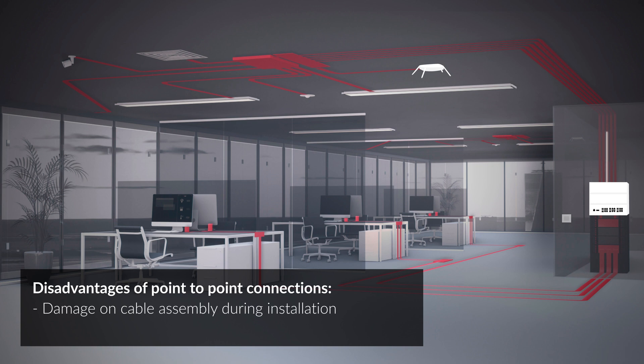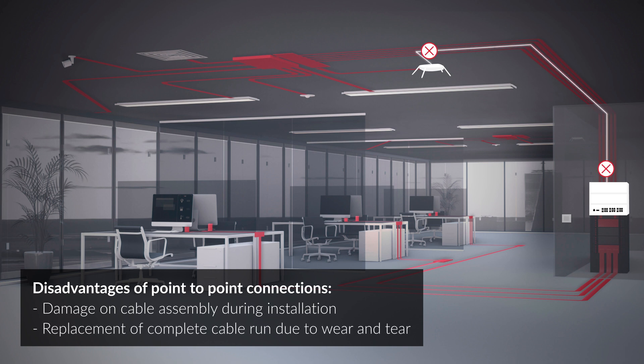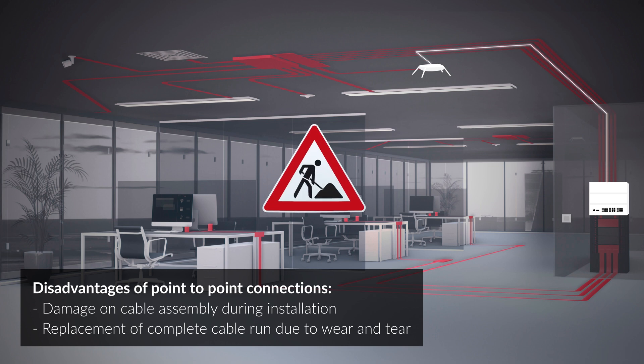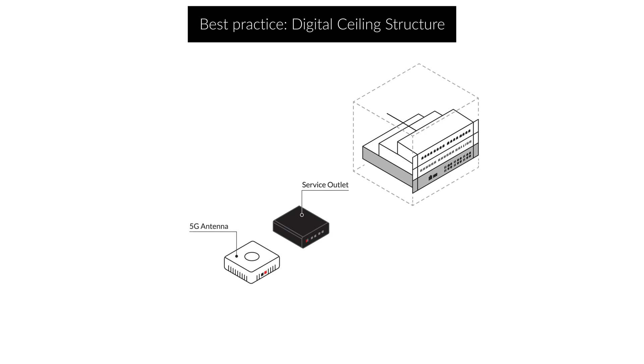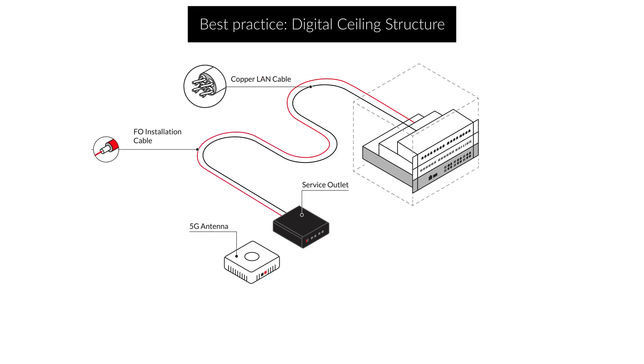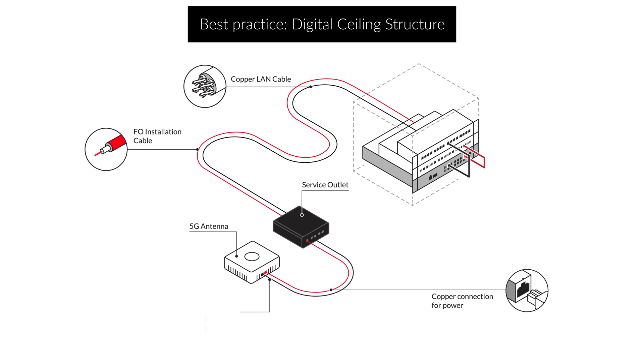During installation of the pre-assembled cabling, a damage loss rate of up to 20% is not uncommon. Wear and tear during operation can demand the replacement of the complete cabling, causing disruption to normal work. Experience and best practice therefore suggest a permanent link design for this application. The installation cables for fiber optic and power will terminate at one end in dedicated 19-inch panels and at the other end in a multi-port box, with network devices then patched using off-the-shelf LC duplex and RJ45 patch cords.